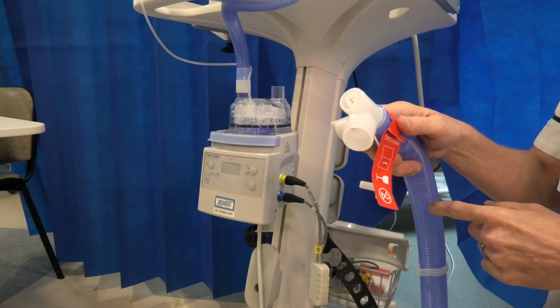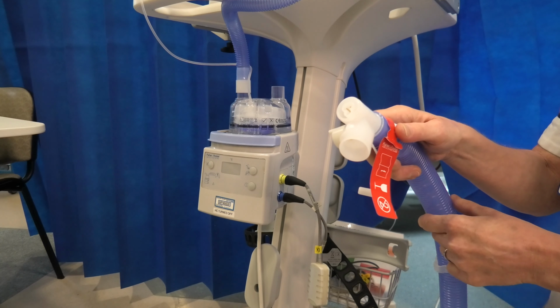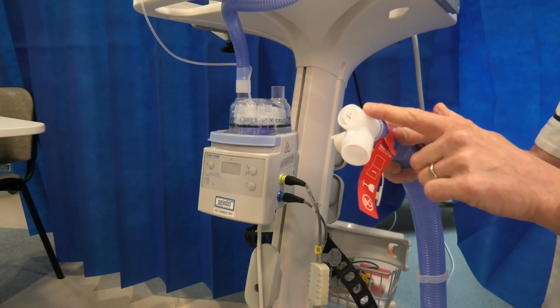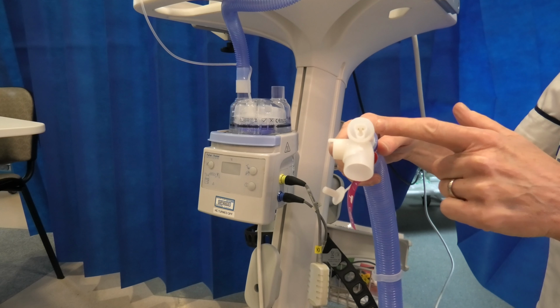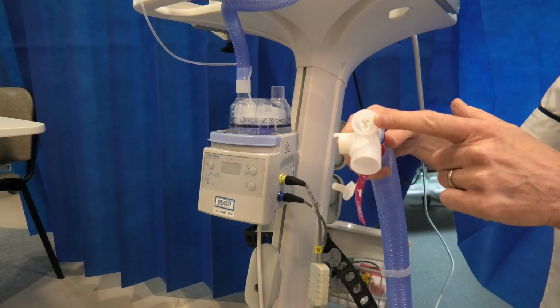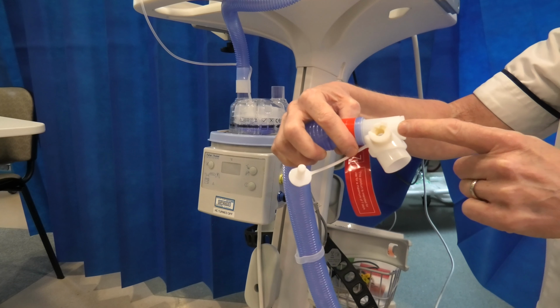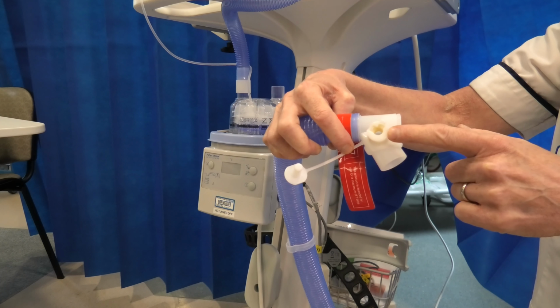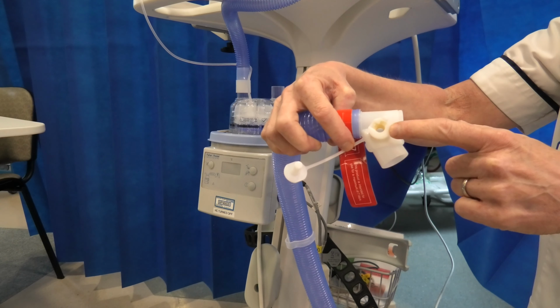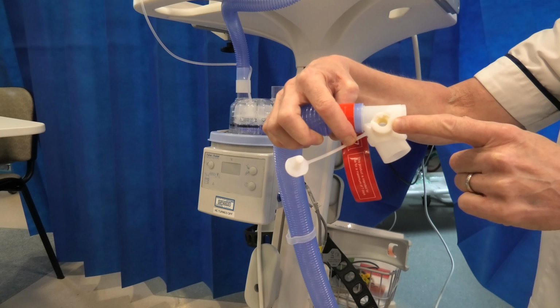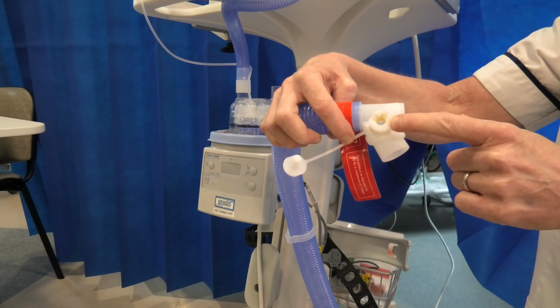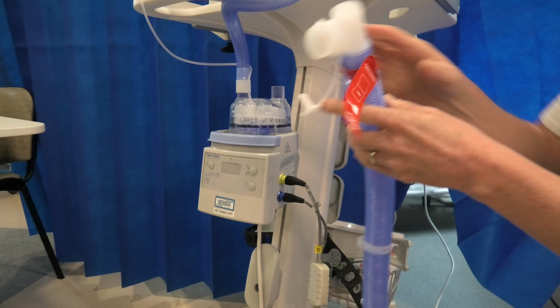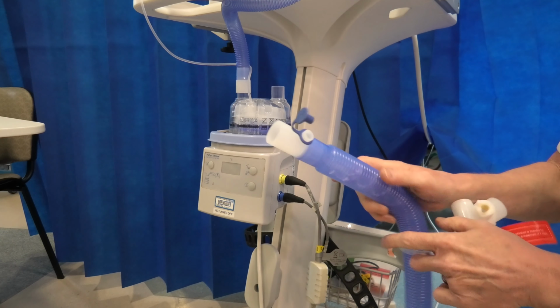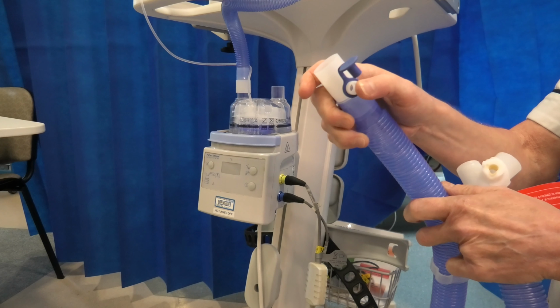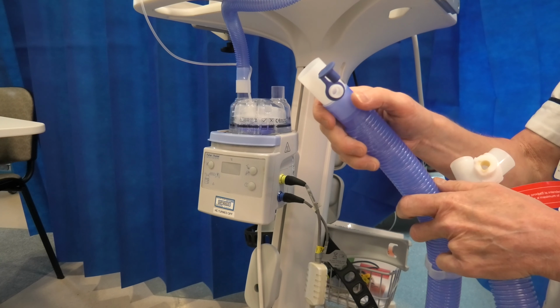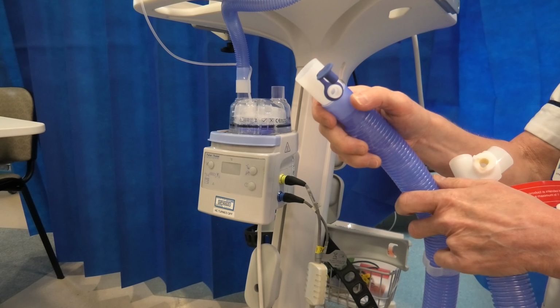So this is the patient end of the circuit. The wide bore tubing goes towards the patient. It's got a really unusual end on it. You can see at the end it's got a clover leaf attachment, and that's where a heater wire goes. And there's another wire that goes in there, which is the blue wire, which tells the machine how hot it is at the humidifier end. At the other end of the tubing, which is directly close to your patient, you would put the other end of the blue wire, which tells the humidifier how hot it is at the patient end.